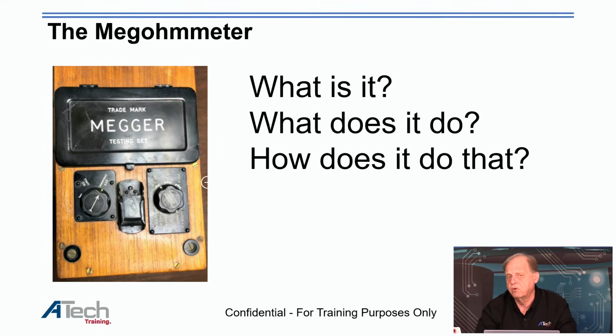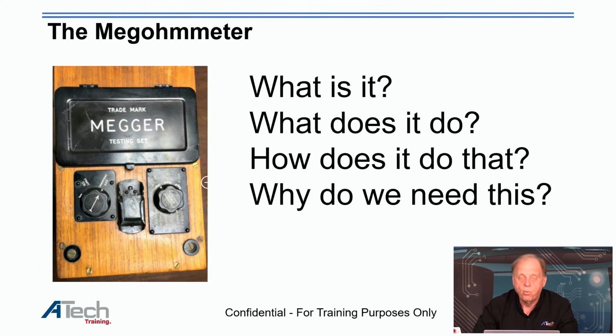Keep this in mind: your conventional meter, when checking resistance, is probably applying under 2.5 to 3 volts, sometimes even less. But we're going to apply 500 volts across this circuit to check the resistance and make sure the insulation is good.